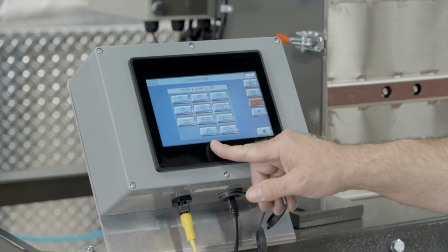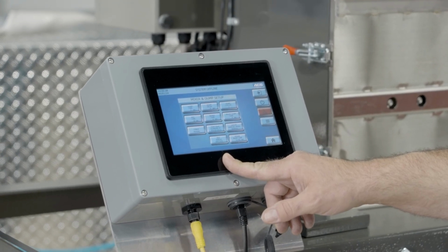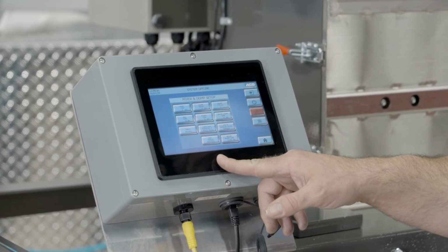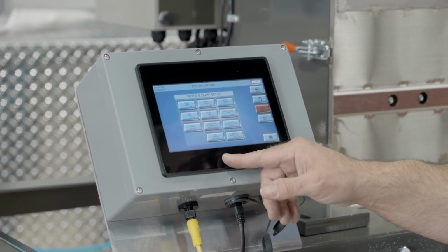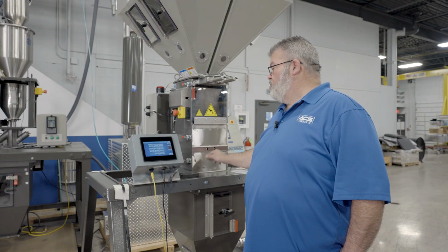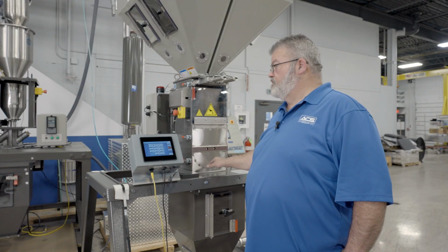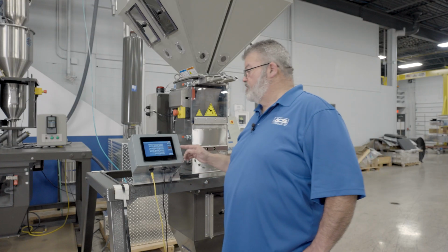And then we're mixing single batches. If you're not getting a homogeneous mix operating in mixed single batches, you can set this to mix to high level. So what that'll do is it won't open your knife gate below the blender until it hits the high level switch. So you'll have more than one batch mixed together in the mixing chamber.